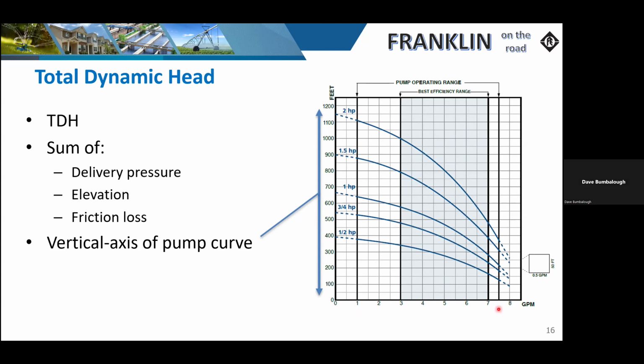Where we want, as a manufacturer, because of efficiency requirements, we want you to stay somewhere in this grayed out area where it's called the best efficiency range. That's where I want to perform. I want my pump sized based on this area here.